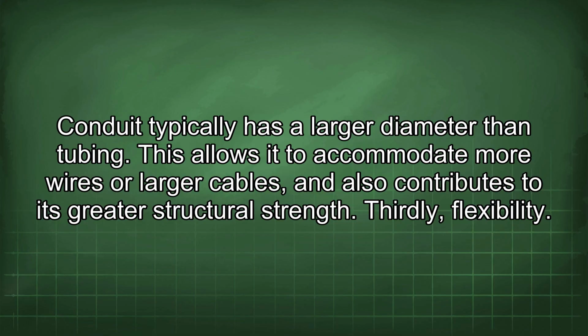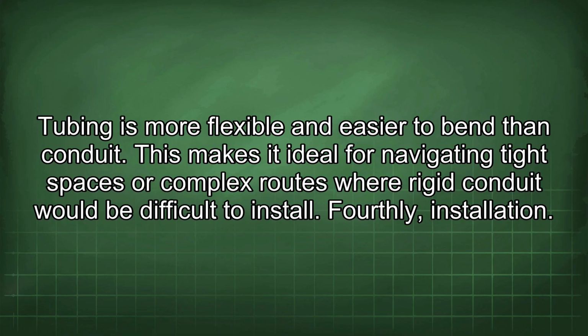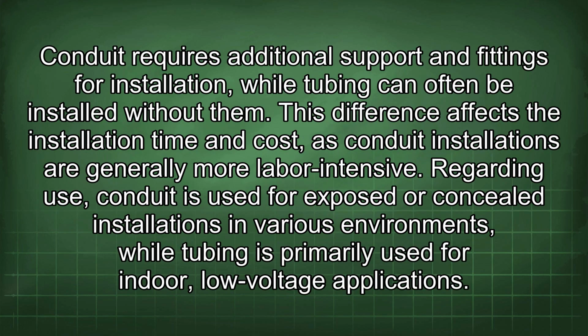Thirdly, flexibility. Tubing is more flexible and easier to bend than conduit. This makes it ideal for navigating tight spaces or complex routes where rigid conduit would be difficult to install. Fourthly, installation. Conduit requires additional support and fittings for installation, while tubing can often be installed without them. This difference affects the installation time and cost, as conduit installations are generally more labor-intensive.